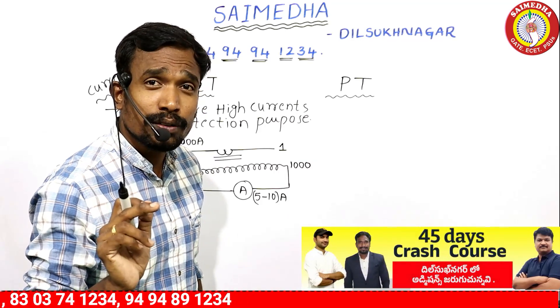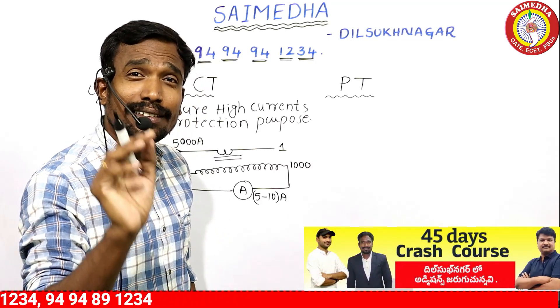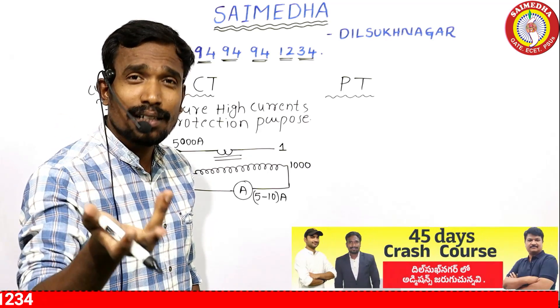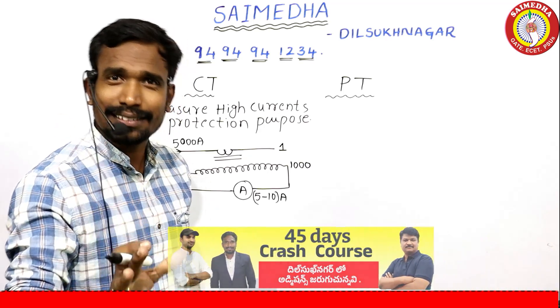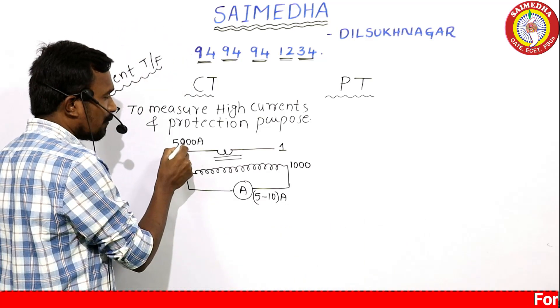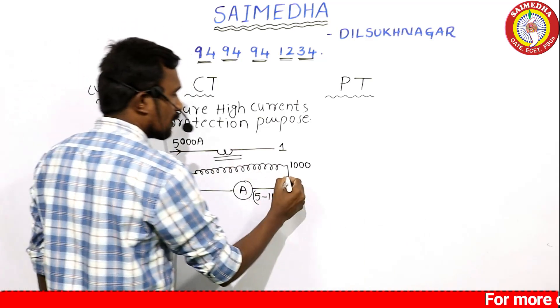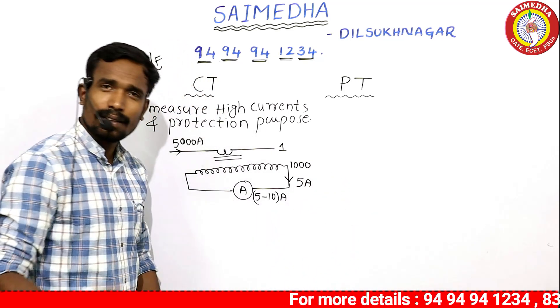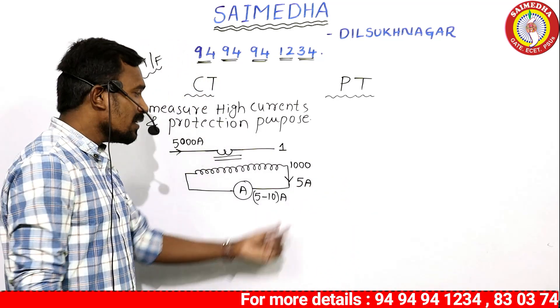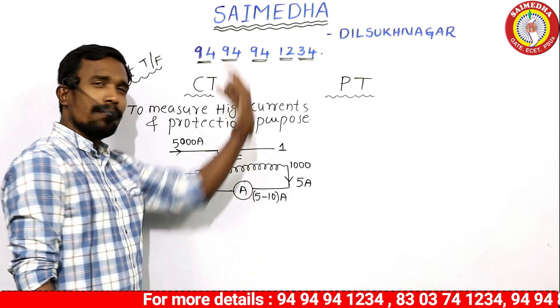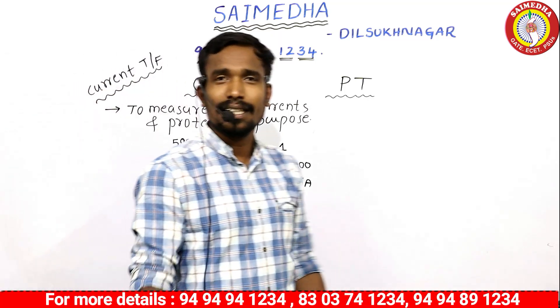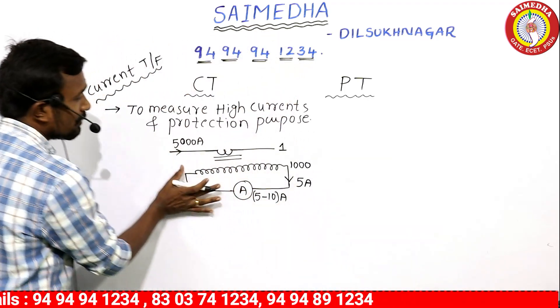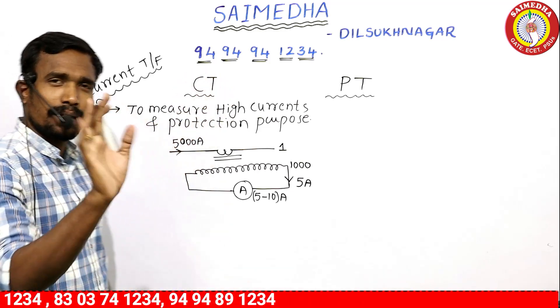The current is stepped down — for example, 1000 times — so 5000 amperes becomes 5 amperes. We measure 5 amperes on the secondary, which represents 5000 amperes on the primary. That is the function of a current transformer.